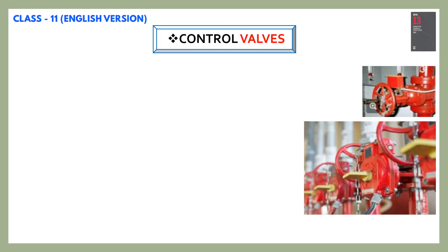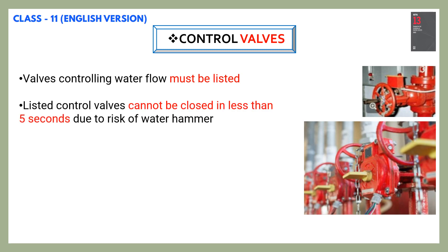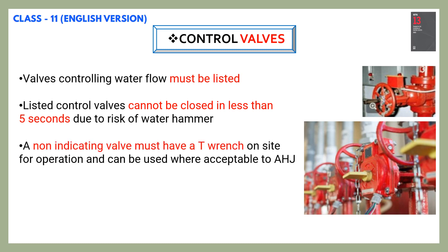Let's have a look at control valves. Control valves can be gate valves or butterfly valves as per NFPA 13. Valves used to control water flow must be listed, and listed control valves cannot be closed in less than 5 seconds due to the risk of water hammer. A non-indicating valve must have a T-wrench on site for operation and can be used where acceptable to the AHJ. The control valve's minimum working pressure is 175 psi.